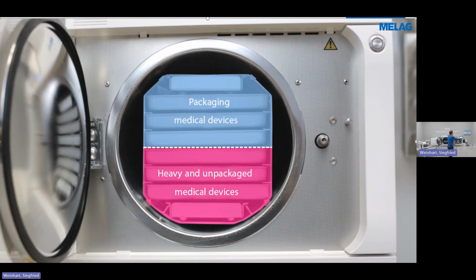I mean, this unit here, for example, will process these 8 trays you see here in 10 minutes. If that was a load of unwrapped instruments, it would do them in 10 minutes, including drying. So there are pieces of equipment that are incredibly quick. This unit will take 2 full-size dental trays. If you were to put 2 unwrapped in there, that's 6.5 minutes. If you were to put 2 wrapped loads in there, that's 15 minutes. So the units are becoming quicker, but you gain the best benefit from them when you maximize the loads that you put into them as well.